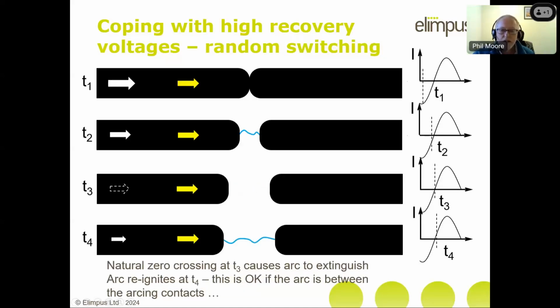Let me try and show you an example of that. So this is one random point where you might separate the contacts, which is at this point here, T1. It's just a little bit after the negative peak. So the contacts separate, and by the time we've got to T2, we've got a nice arc burning there. But by the time we get to T3, the contacts aren't fully separated, but they're a reasonable distance apart, and the arc now goes out. Then a little while later at T4, the transient recovery voltage caused by the reactor transient causes the arc to restrike or reignite, to use the proper terminology.